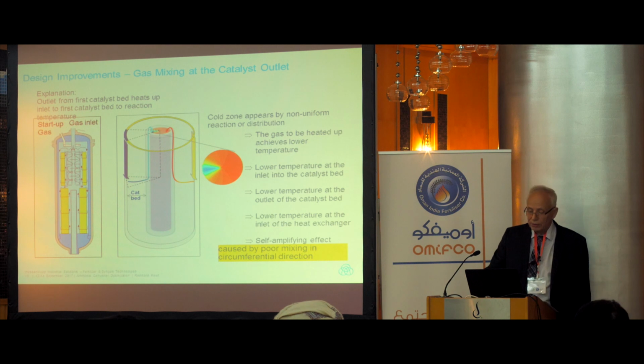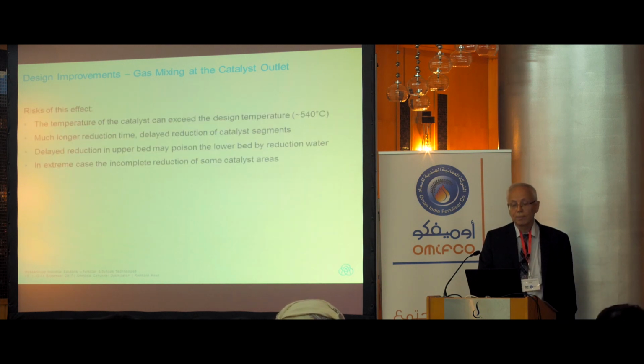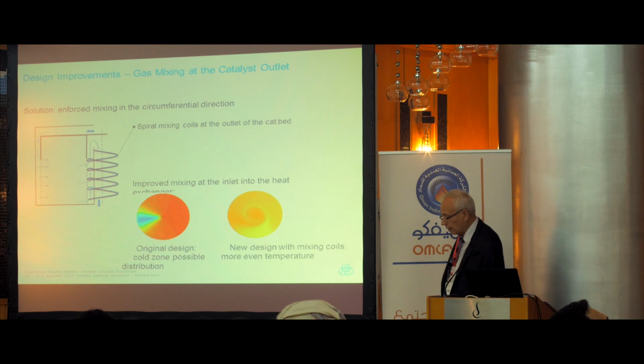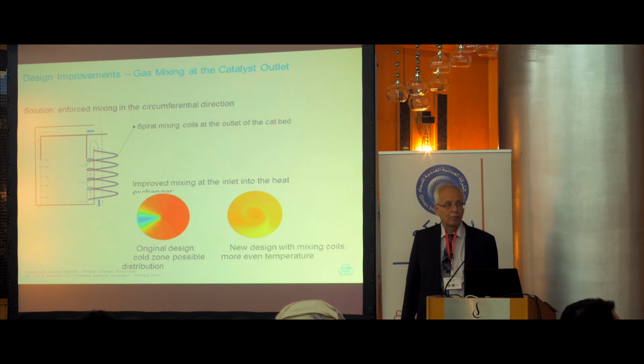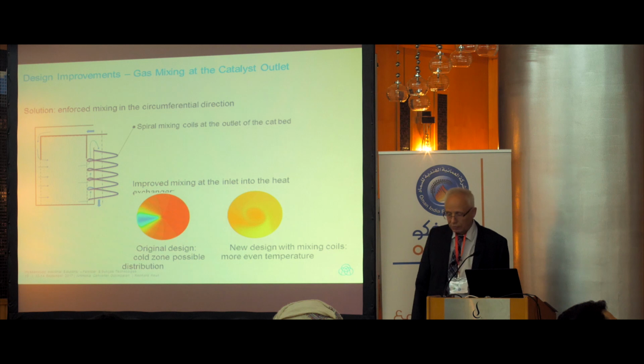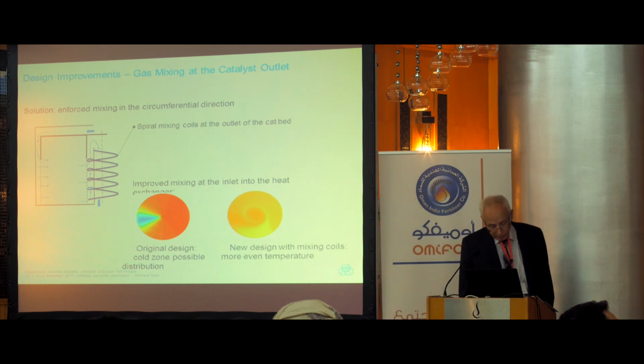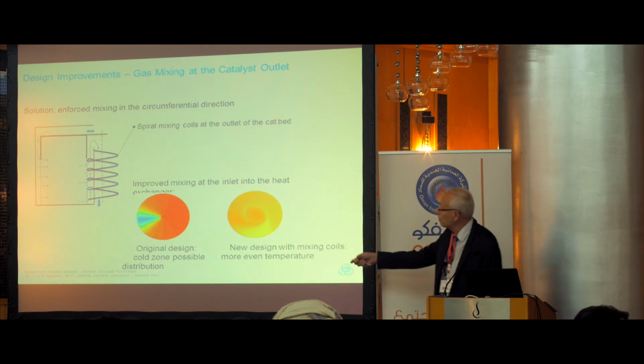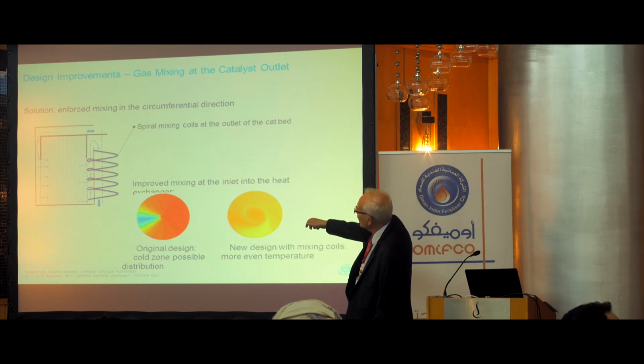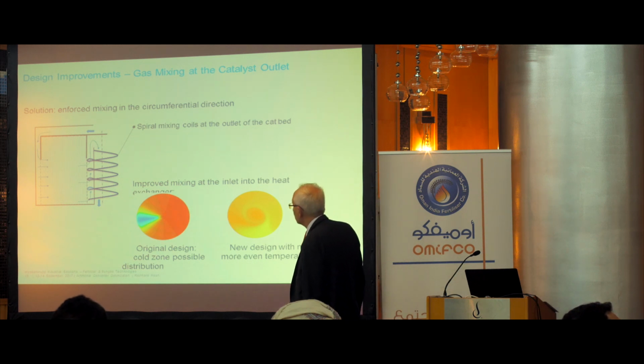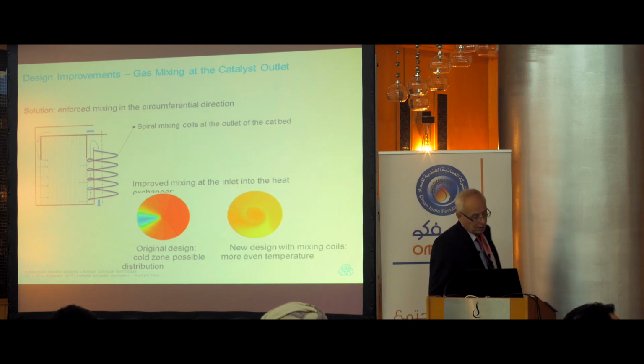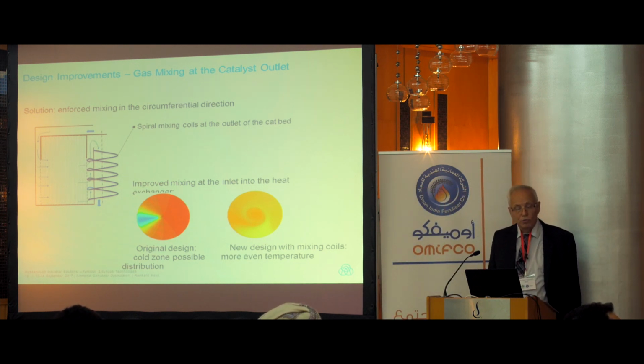And to get rid of it, we found a solution which can be easily installed, but of course not later. That can only be done together with a catalyst replacement. It is a part which will be inserted at the outlet of the catalyst bed, and it's a spiral mixing coil, and that improves the mixing in this circular room around the catalyst bed, and by that it leads to a uniform gas distribution.